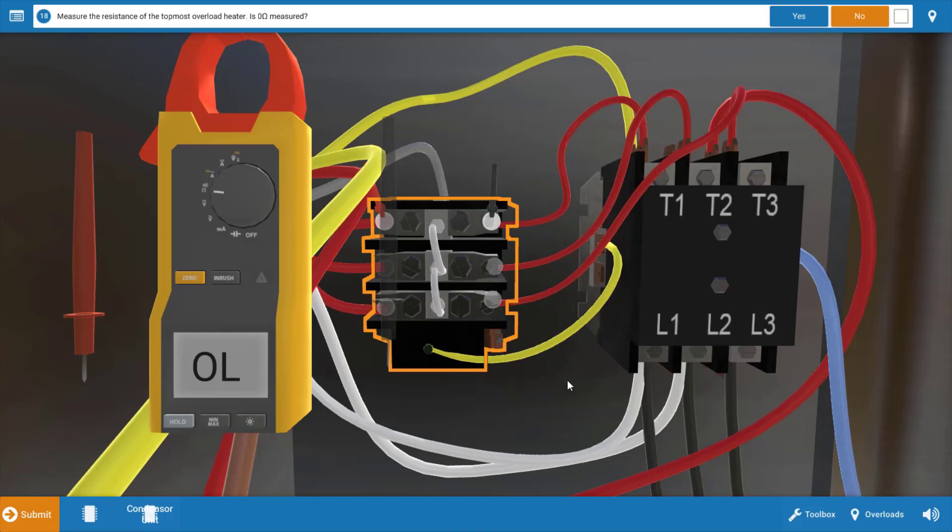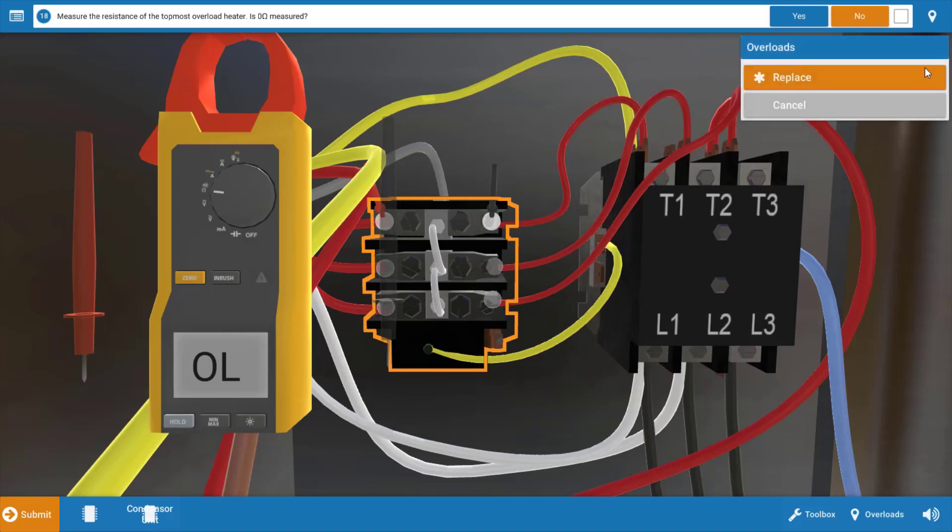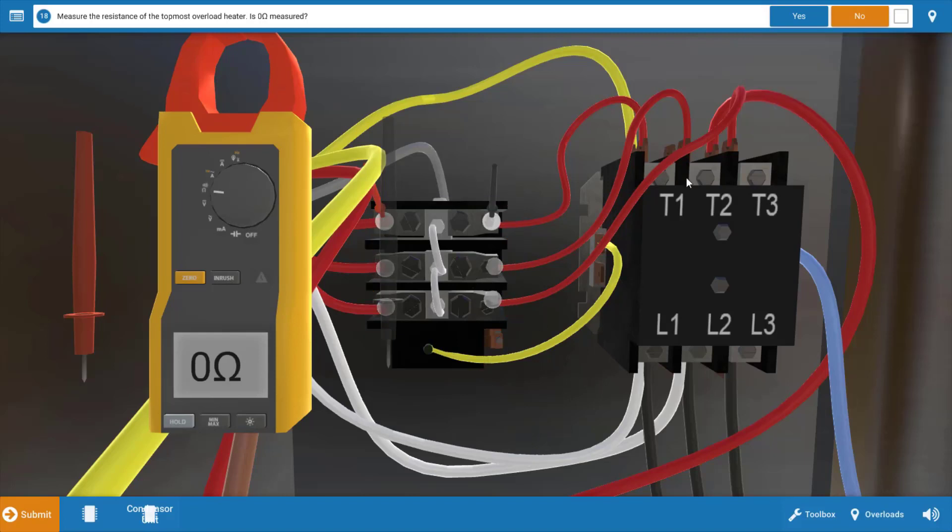We obviously have a heater problem here. We're going to need to replace the overload. We're going to click on it and click replace, and this is going to solve our problem. We can see we go to zero ohms now once we've fixed the problem.